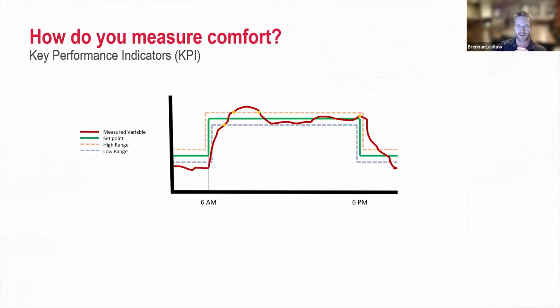This is an example of, say, an office, a school, any zone in a building, really. Let's take that temperature thermostat. The green line is the set point, the red line is the actual. So what analytics will do is analyze everything in your building. It'll define parameters, what's good and what's bad, and how long it is within that range. And it'll use its algorithms to figure that out.